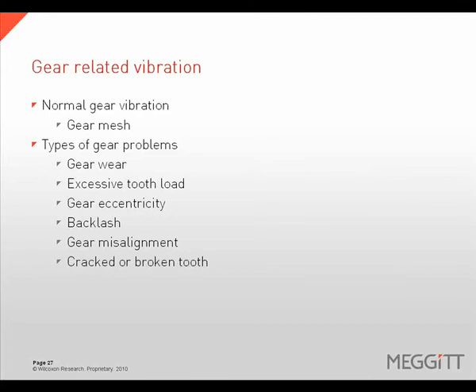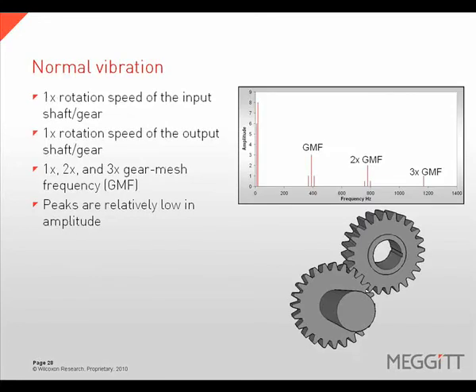Any gear set will generate a vibration response — gear-related vibration can be normal, or it can indicate problems such as gear wear, gear misalignment, or cracked or broken teeth. It is normal for a gear set to generate vibration at its gear mesh frequency and its harmonics; 1 times, 2 times, and 3 times gear mesh frequency are all normal, but they should be at relatively low amplitudes.